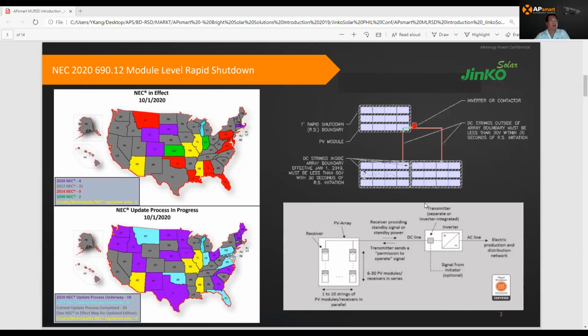Basically, what they require is two parts. One, you can see, is the transmitter, which is on the inverter side. The other device is the receiver, which is located on the module side. The function is the transmitter sends over what we call a heartbeat signal, which is PLC communication, through the power line to the receiver.